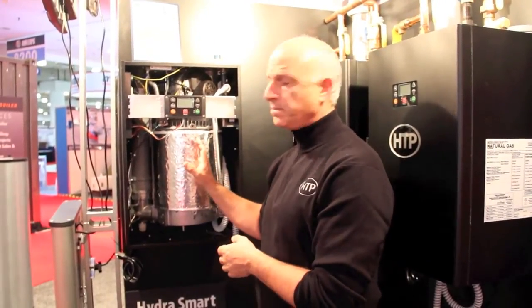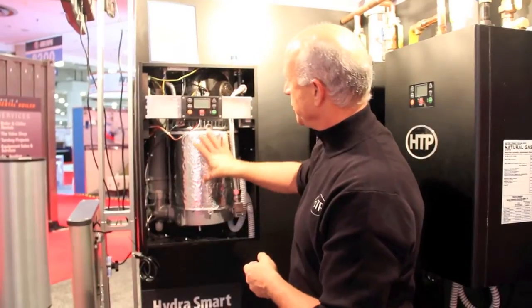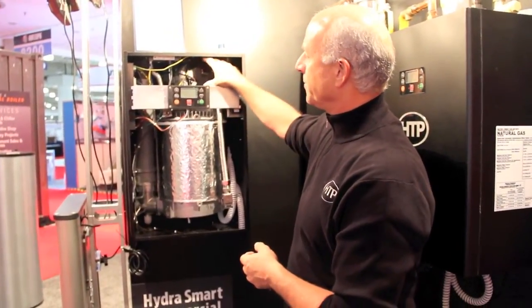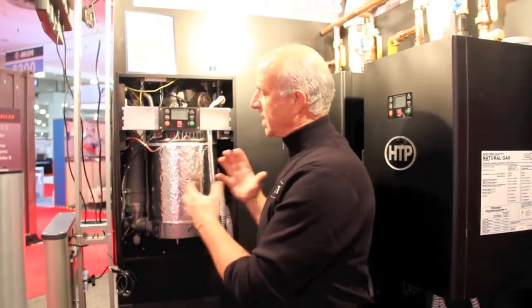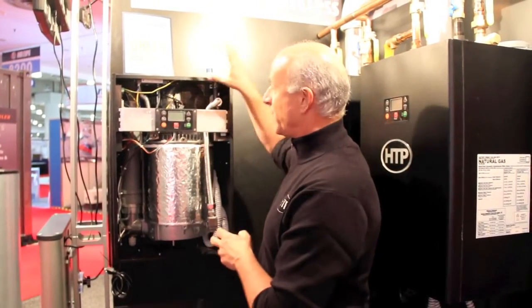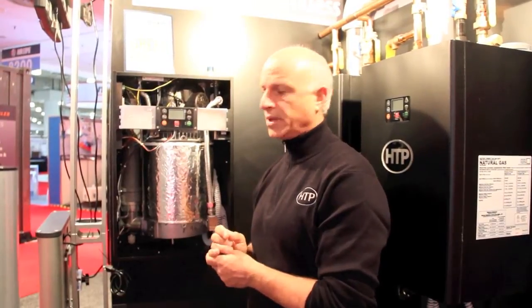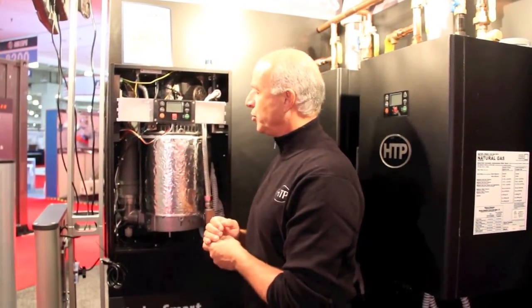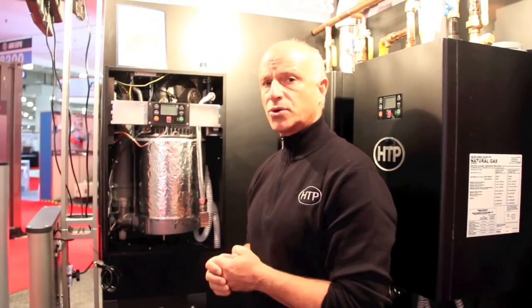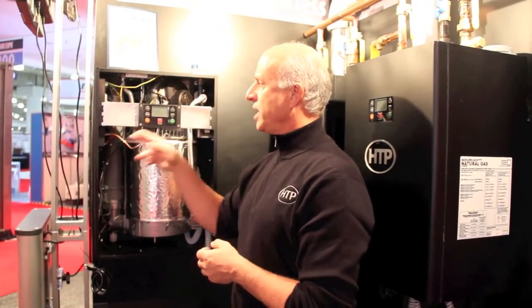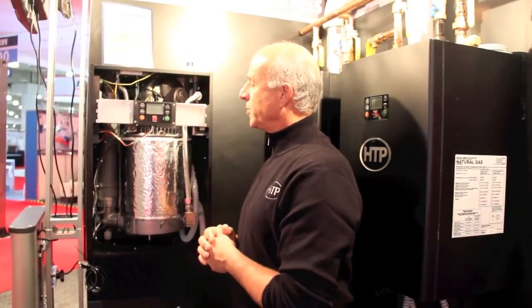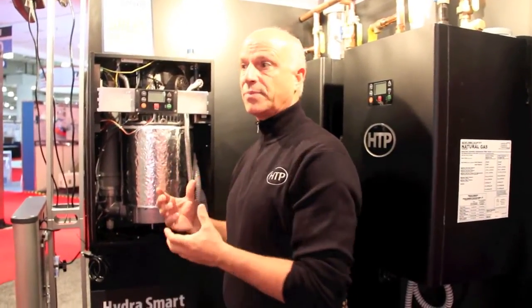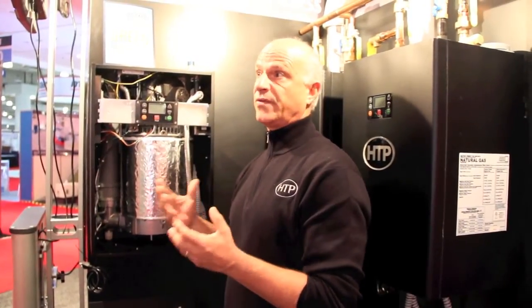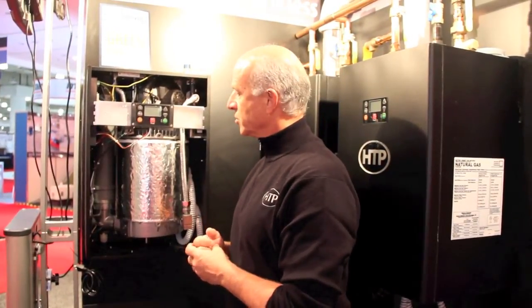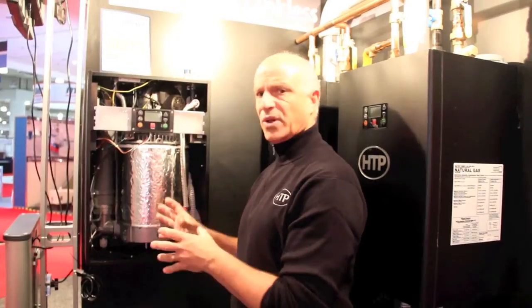This is 250,000 BTUs. This is the primary heat exchanger here, and then your combustion system is up here. The unique thing about this is you can put 10 of these together in a manifold system, and you can manifold your vent, so you have a single penetration in the building. It has a masterless control system built in, so all you do is daisy chain multiples, up to 10 of them. So you can imagine if you've got 10 of these in a system, you're up to 2,500,000 BTUs, and you fire all the way down to 30,000 BTUs. So it's got a lot of power, 8-to-1 turn down, really built for commercial.